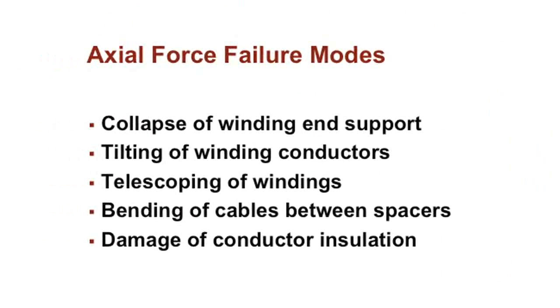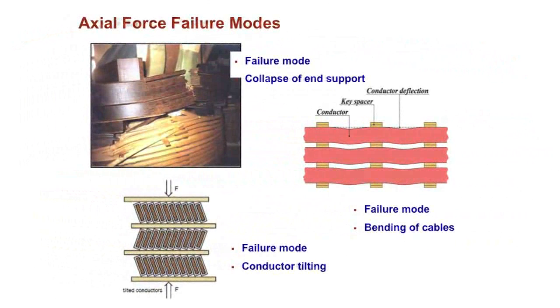So during a short circuit event, the winding end support can fail. These are huge blocks that hold the windings together and that are clamped against the clamps. You could have tilting of the conductors, and the windings can telescope. The cables between spacers can bend, and you can have damage to the conductor insulation. And as I said, a transformer could survive this, and it could be something else later that fails in some kind of dielectric event. So this is where it's trying to become much bigger. These are the types of failures you can have.